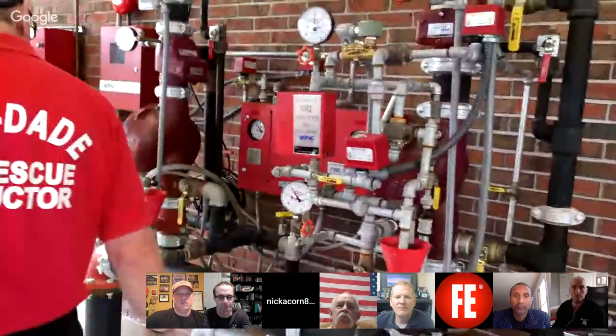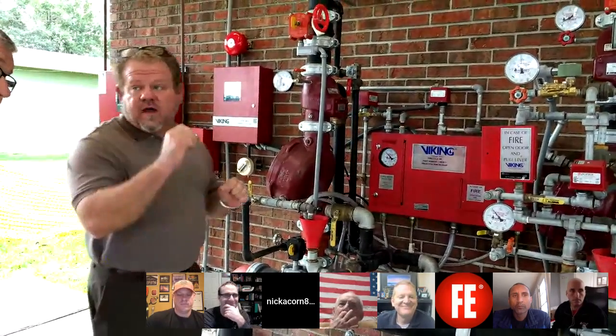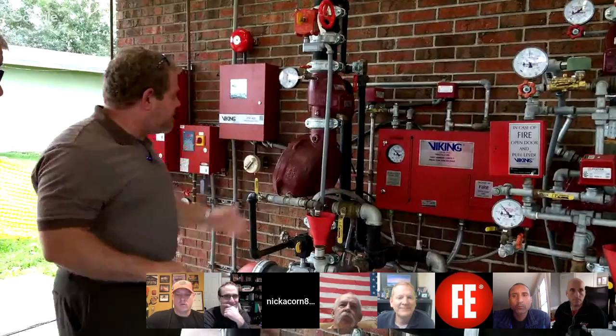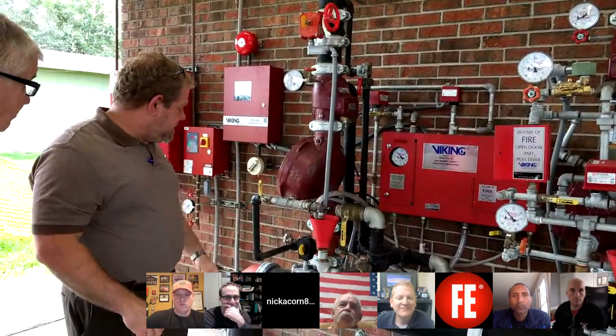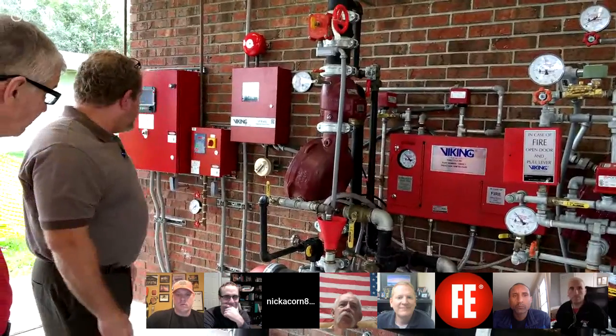This is a really neat system to me because this is essentially on-off fire protection. This is a fire cycle system with a proprietary detector. The detector activates the system upon discharge of the fire sprinkler system. The area cools, and the detector actually allows the solenoid valves, one to open, one to close, and reverse operation, and it shuts itself off. This system resets without ever closing the control valve. Really, really neat. There are several different applications for this. Without any human intervention, it'll turn itself on and turn itself off. Oh, excellent. Really, really neat.